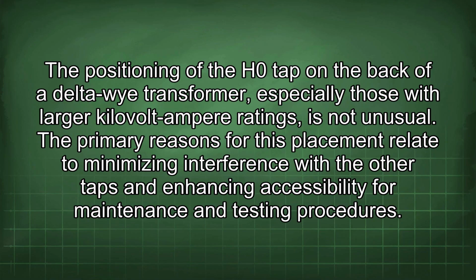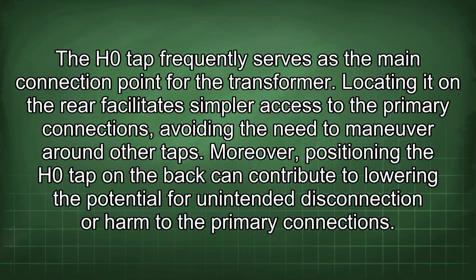Positioning of the H0 tap on the back of a delta-wye transformer, especially those with larger kilovolt-ampere ratings, is not unusual. The primary reasons for this placement relate to minimizing interference with the other taps and enhancing accessibility for maintenance and testing procedures. The H0 tap frequently serves as the main connection point for the transformer.